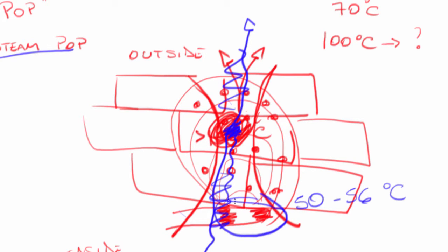So you normally set this at anywhere between, I've seen anywhere between 50 and 56 Celsius if the temperature on the surface, and this is for some catheters, other catheters are different. So if the temperature on the surface reaches this point the machine will shut off automatically. So you say I want to warm up and burn everything but if the temperature goes above 52 I want you to automatically turn off the power because I'm not, I'm doing the ablation, I'm not looking at everything at the same time. I have to trust my equipment and the equipment help me to prevent steam pops by doing this, by turning itself off.